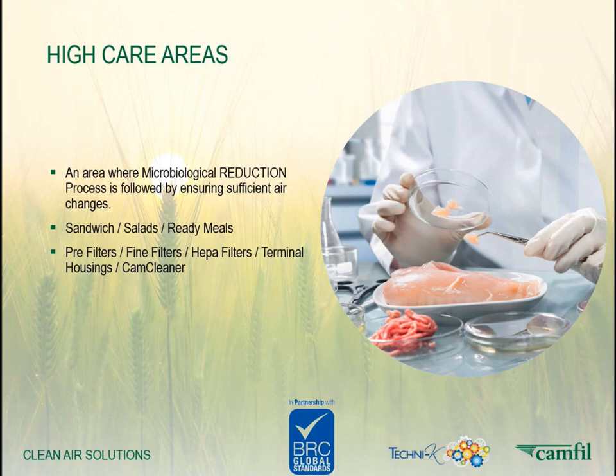High care areas. This is an area where a microbiological reduction process is followed by ensuring sufficient air changes. Examples are sandwich production, salads, and ready meals. The same first stage filtration as basic care areas can be utilized here. Second stage filters should again be at a very minimum F7 or ePM1 50%. Final filters should be HEPA, and to ensure compliance, these filters should comply with EN 1822. Your risk assessment will help identify the level of HEPA filtration needed in these areas.